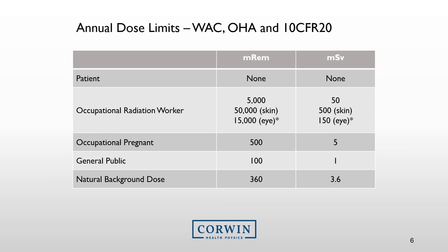The annual radiation dose limits come from Title 10, Code of Federal Regulations, Part 20, which specifies that occupational radiation workers can only receive 5,000 millirem total effective dose equivalent, or 50 millisieverts. There are additional dose limits for other parts of the body: the skin can only receive 50,000 millirem and the eyes can only receive 15,000 millirem. Patients, however, can receive any dose that the doctor has deemed necessary for their procedures or diagnostic studies — there is no limitation on patient radiation dose.